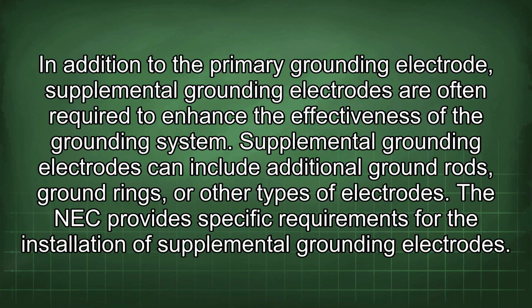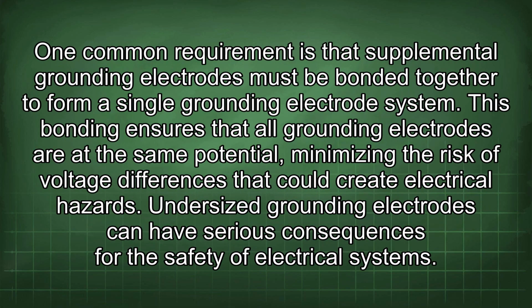In addition to the primary grounding electrode, supplemental grounding electrodes are often required to enhance the effectiveness of the grounding system. Supplemental grounding electrodes can include additional ground rods, ground rings, or other types of electrodes. The NEC provides specific requirements for the installation of supplemental grounding electrodes. One common requirement is that supplemental grounding electrodes must be bonded together to form a single grounding electrode system.